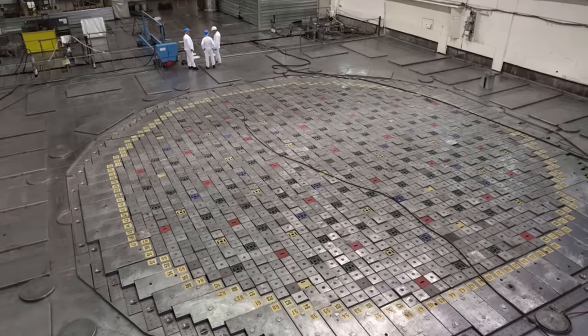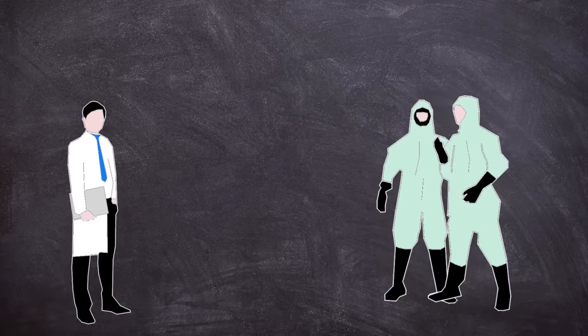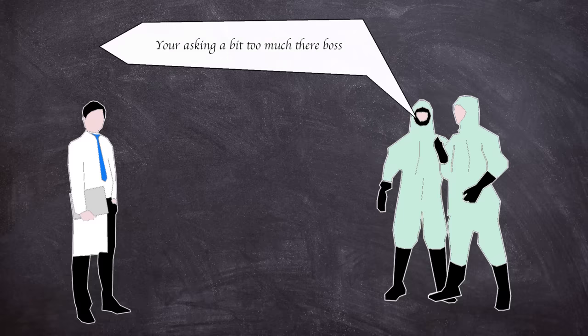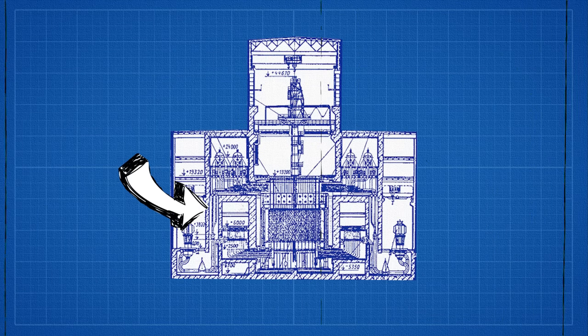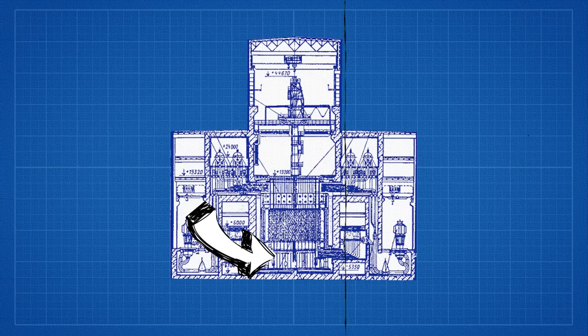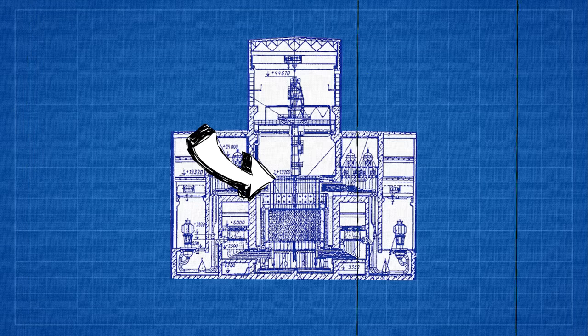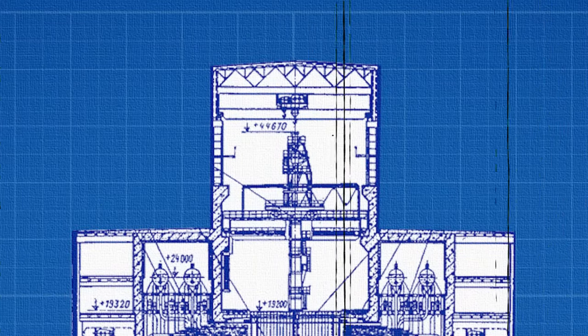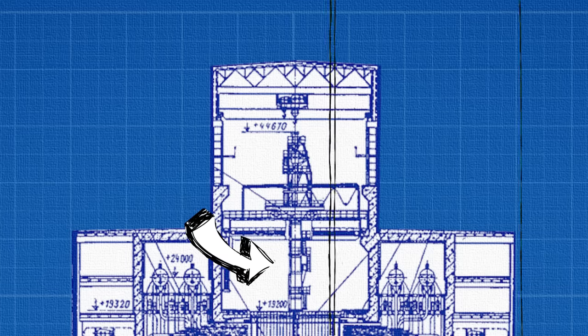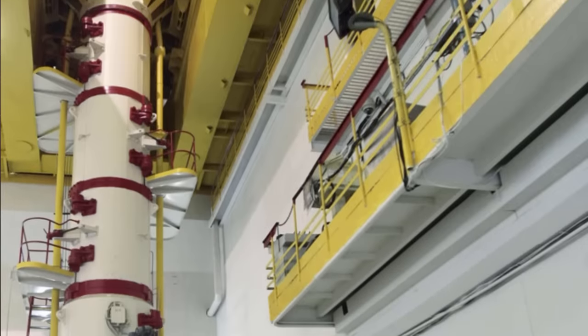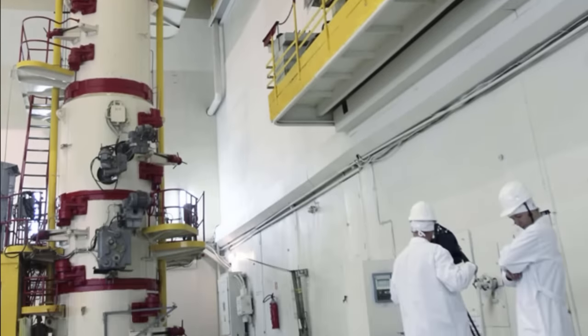The final part of the RBMK was its containment, or lack thereof. You see, the doctrine at the time of the RBMK was that it was always going to be operated within design specs, hence no risk of disaster. This didn't take into account human nature for buggering things up. What little protection to the outside world was provided was in the form of a reinforced concrete lined cavity that acts as a radiation shield. The reactor itself sat on a steel plate and was topped by a thousand-tonne steel cover. The steam separators were also housed in their own separate concrete containments. A contributory factor to the lower containment than other reactors was that it can be refueled whilst in power operation. To achieve this, a large crane is situated above the reactor. This meant that building a massive concrete dome containment structure would be time-consuming and, more importantly, costly.